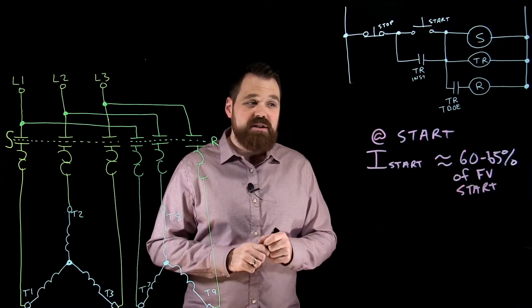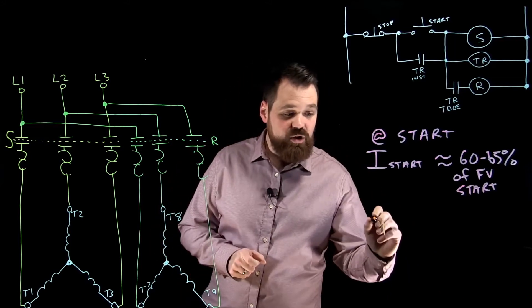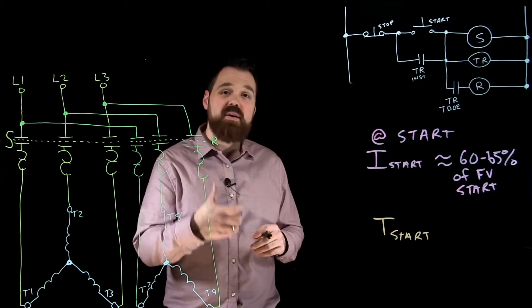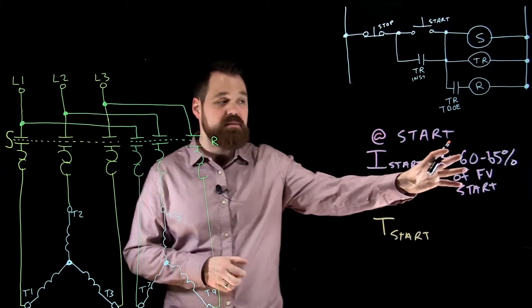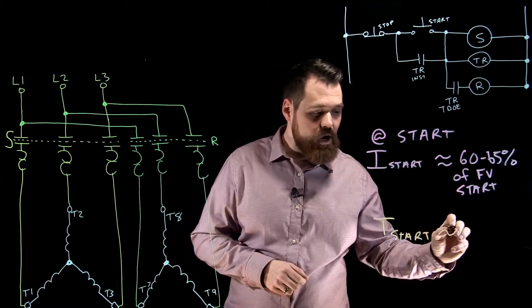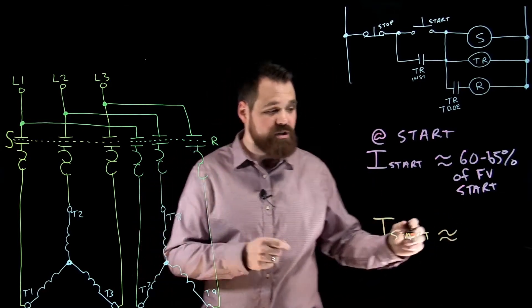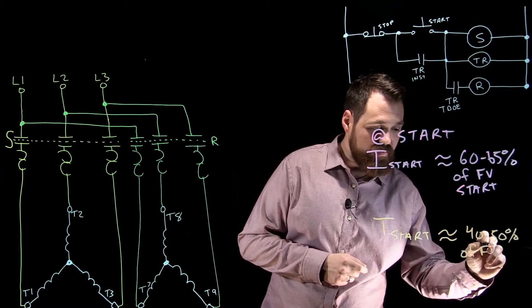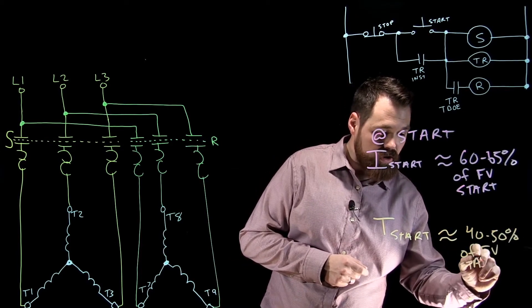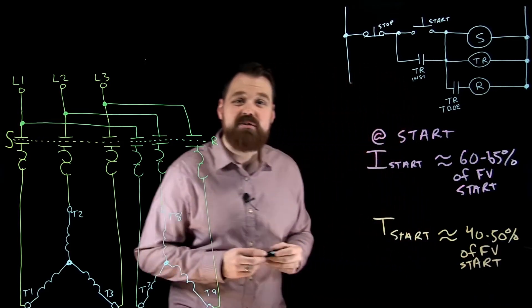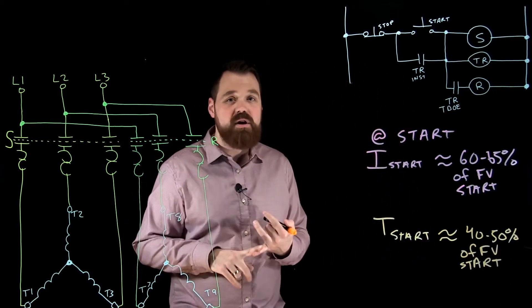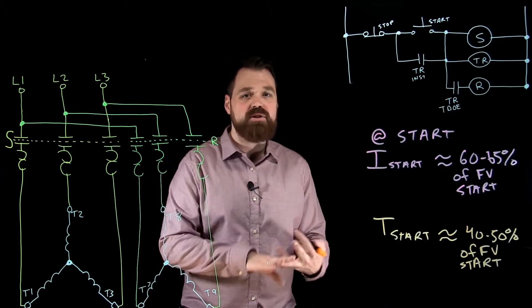One of the issues that we see with this motor is that my torque at start is very poor. So I'm not going to get the 60 to 65%, and just depending on the motor, you're actually going to get about 40 to 50% of what we call our full voltage starting torque. So these motors are specifically for loads that are either no load at start or a very low load at start.